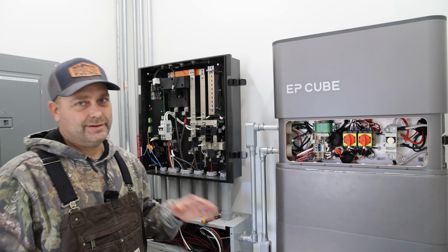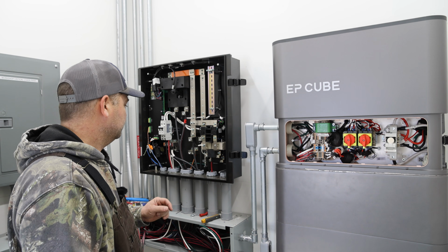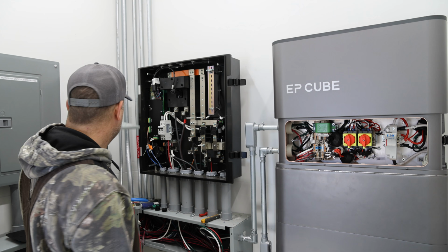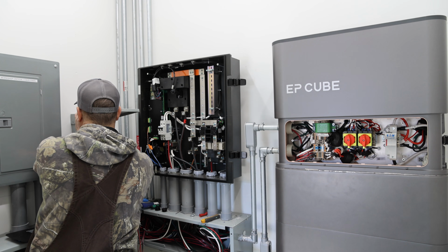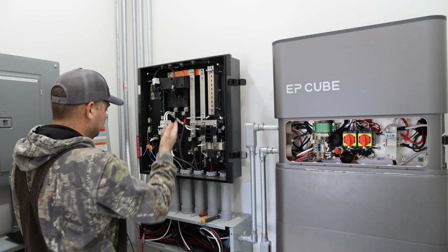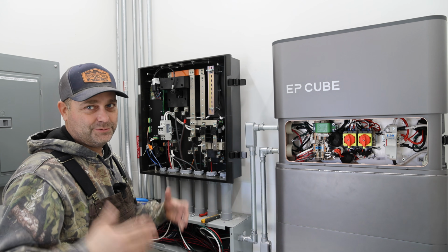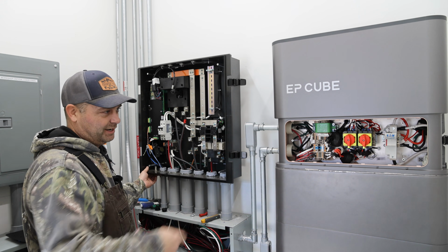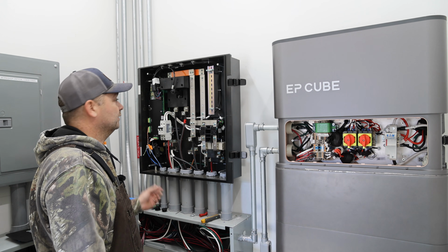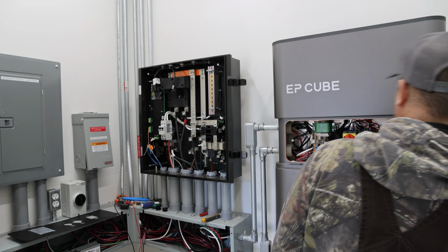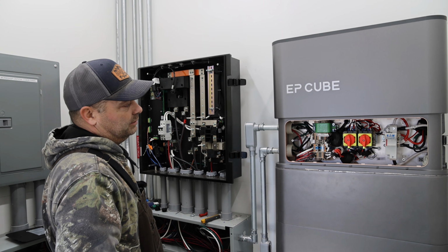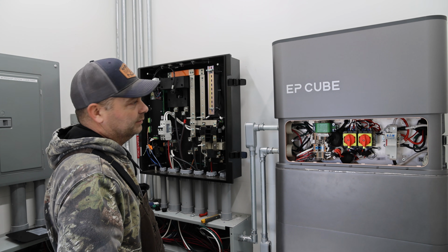So everything's wired up now. I think I'm ready to go ahead and power this up. So I think the first thing to do, we'll throw the battery fuse in. We'll go ahead and turn on the grid power. You have to have grid power to start this up from being completely dead. It won't start up off the batteries the first time. So power up the gateway. Go ahead and power up the inverter. Oh, the inverter doesn't seem to be powering up.